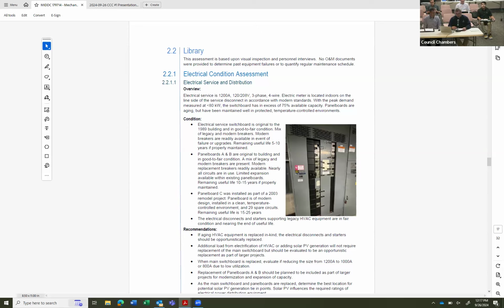as to the cost benefit of downsizing that service, since it's looking like it's around 20 to 25% utilized. You can have some significant cost savings by going down to, say, an 800 amp service from a 1200 amp, and still have plenty of capacity. Then you have a smaller form factor of the equipment that takes up less space, and smaller wire size, which also has a cost savings. And with the increase in the cost of material over the past few years, it could end up being a cost savings that could fund other items. Here again, there is plenty of capacity to support any electrification of loads.